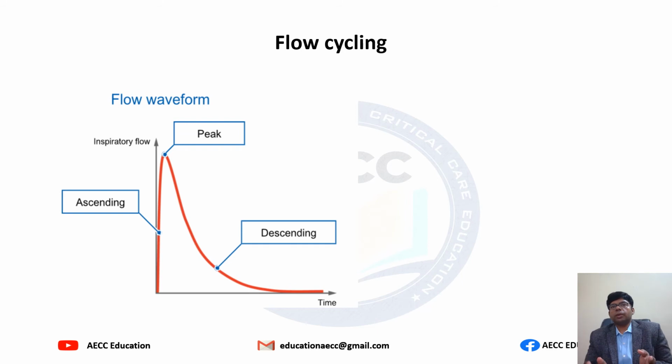So by setting the inspiratory time, I:E ratio, and peak flow, we can manage the time cycling. Peak flow is only helpful for the volume control mode because there is constant flow. In case of the pressure mode, the flow is not constant, flow is mainly descending. Hence, the peak flow is not one of the setting criteria for controlling the cycling in case of the pressure control ventilation. After time cycling, let's move to the flow cycling.